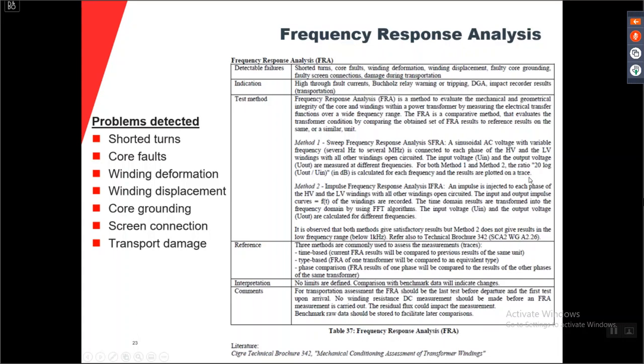And for this, when we look at the interpretation, the reference is that your new measurement should be the same as your old measurement. So you need to have something to compare with. There are no limits defined. You need to have comparison with benchmark data. Very often, the SFRA measurement has been done when you have found a fault. And then you would like to say, is this okay or not? But if you don't have anything to compare with, it can sometimes be difficult.